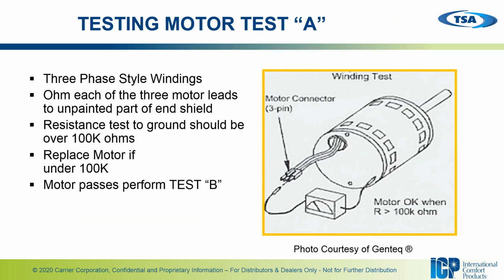All right, so variable speed or ECM motors are three-phase type windings. So you're going to ohm out each of the windings from one to another. You should see less than 20 ohms. If you test them to ground for a short, you should see well over 100,000 ohms. If you're under that, that means the motor's grounded or shorted, if you will. You want to measure each one of those windings to ground to make sure each winding is not grounded.